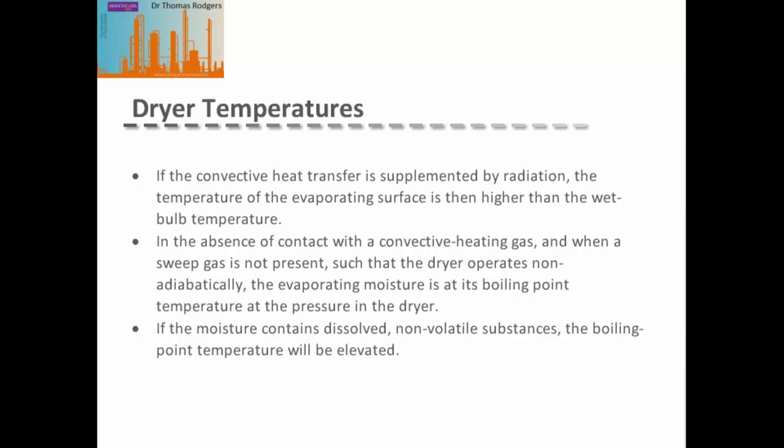If convective heat transfer is supplemented by radiation, the temperature of the evaporating surface can be higher than the wet bulb temperature. In the absence of a convective heating gas and sweep gas, such that the dryer operates non-adiabatically, the evaporating moisture is at its boiling point at the pressure inside the dryer. If the moisture contains dissolved non-volatile substances, the boiling point temperature can be elevated.